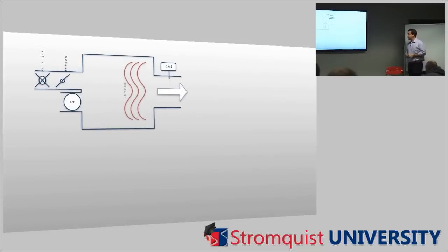All right, this is a typical VAV box. This is not drawn to scale. This is what you may or may not see up above your ceiling in a VAV box. And for those of you who don't know, we don't have any here, but you see them in large commercial buildings where you have the air handler units. That's its whole job, to push 55 degree air down the ductwork. And then the VAV boxes are over each zone, and they have a damper up here that opens and closes depending on what the space temp needs to be in that building or that zone, right?